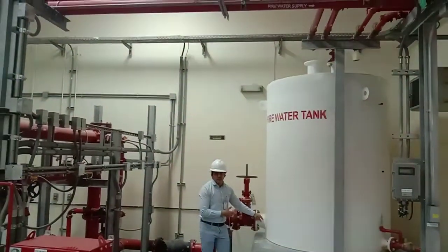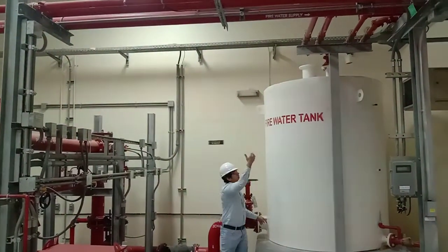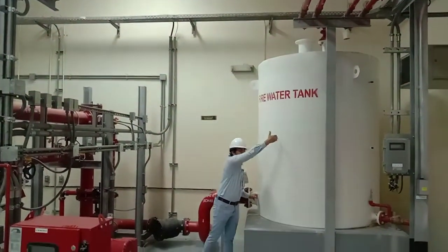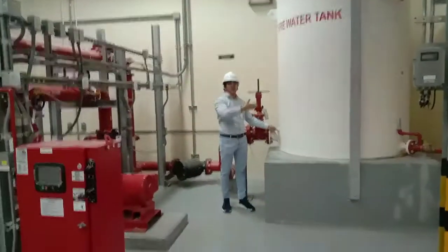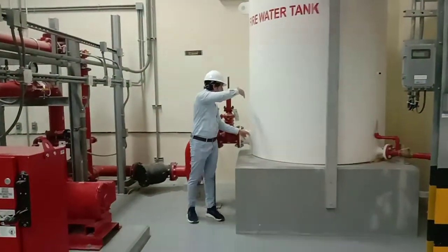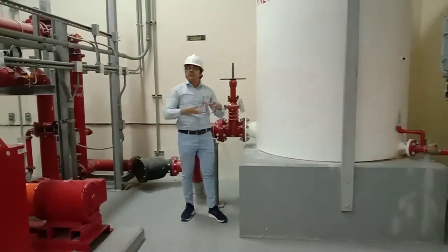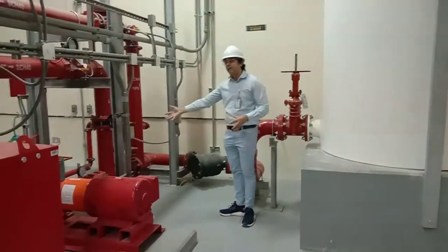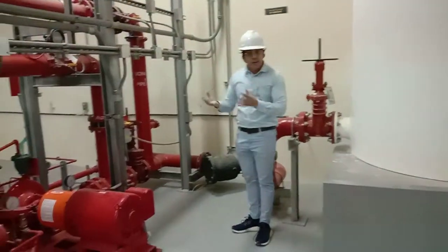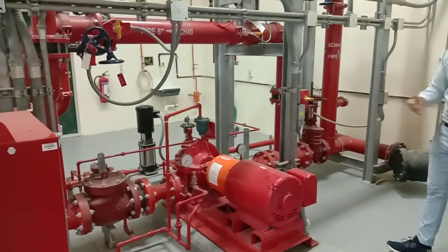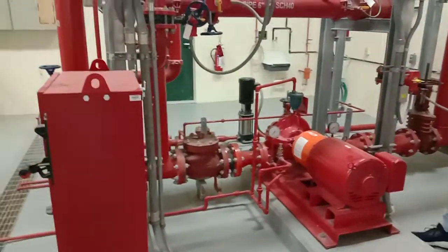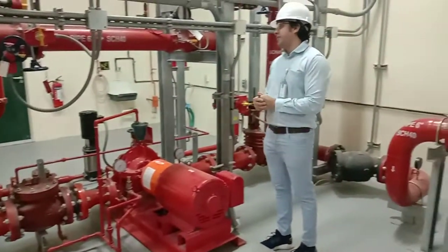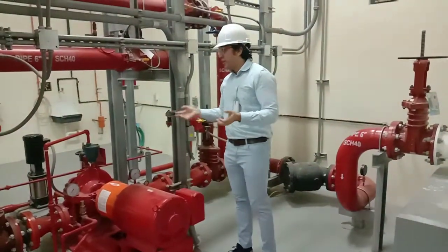Right? Here is the suction connection. So the discharge lines, the return lines, should be some distance away from that, because we don't want that water discharging directly near the suction connection and creating turbulence. Now that turbulence will go all the way from the suction line to the impeller of the pump, and it will cause cavitation. Cavitation is not good for the pump. It will damage the pump impeller capacity, and it's not a good practice.